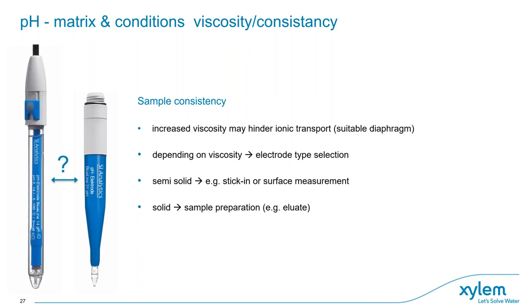If the viscosity is higher, this can hinder ionic transport. Depending on viscosity, you may need to choose another electrode type — for semi-solid samples, a stick-in or surface measurement electrode may be needed; for solid samples, sample preparation such as an elution is required and measurement is done in the aqueous phase. In many cases, even for soft cream or soft cheese, a refillable glass electrode is recommended over a stick-in electrode because it can be refilled, cleaned, and maintained, and it costs less. A stick-in electrode is more robust for harder materials like hard cheese or meat.